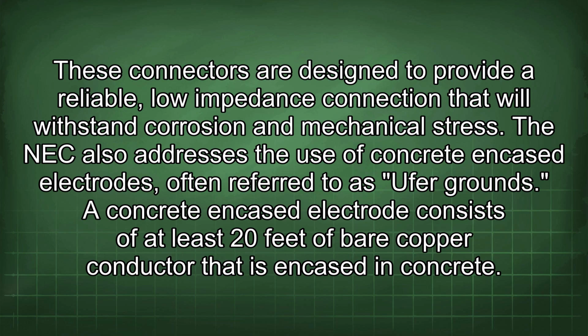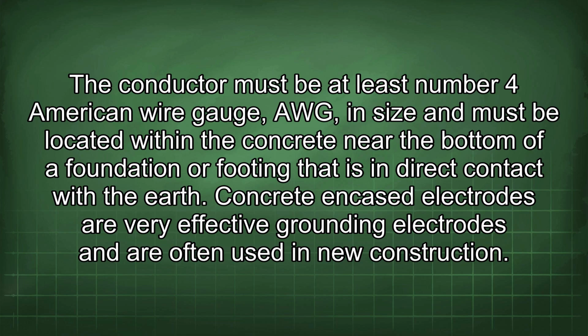The NEC also addresses the use of concrete-encased electrodes, often referred to as Ufer grounds. A concrete-encased electrode consists of at least 20 feet of bare copper conductor that is encased in concrete. The conductor must be at least number 4 American wire gauge, AWG, in size and must be located within the concrete near the bottom of a foundation or footing that is in direct contact with the earth. Concrete-encased electrodes are very effective grounding electrodes and are often used in new construction.